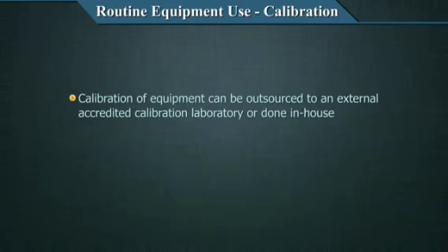Calibration of equipment can be outsourced. That's another thing that I would like to bring to your attention: to an external accredited calibration laboratory, or this can be done in-house also. Generally in India as of now, it is getting outsourced, but it can be done in-house also. We have already talked about the outsourcing of calibration to calibration laboratories. We are mostly talking about minor equipment, ancillary equipment like pipettes, centrifuges, etc.